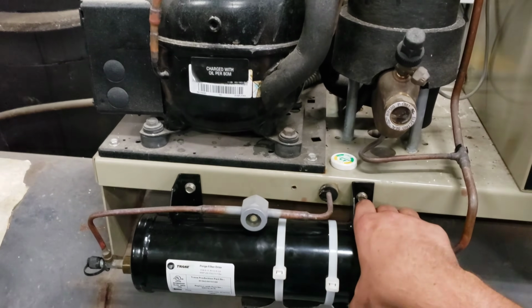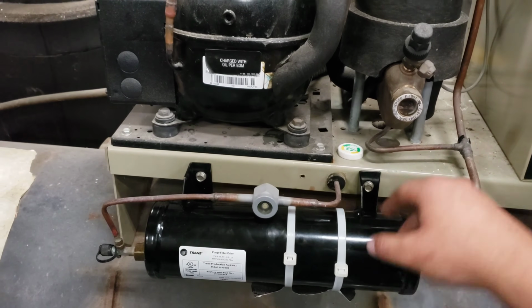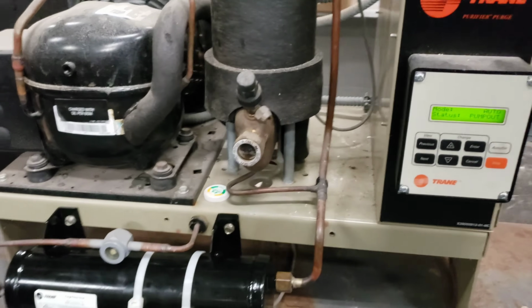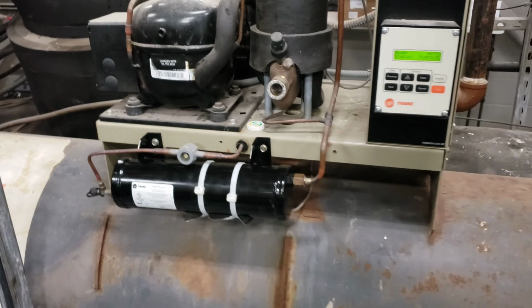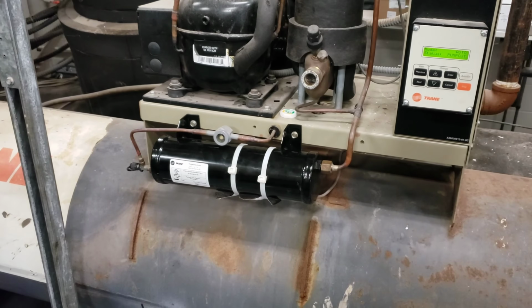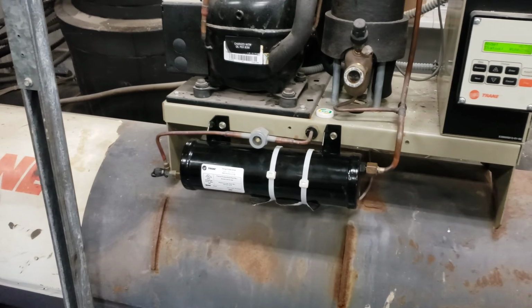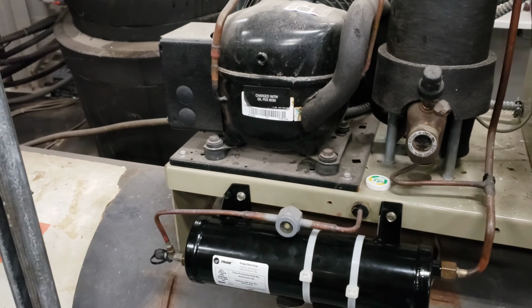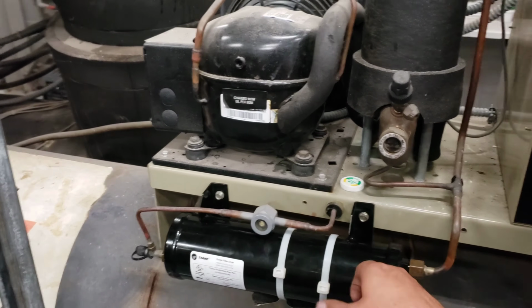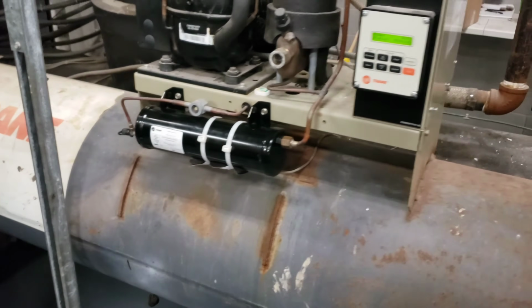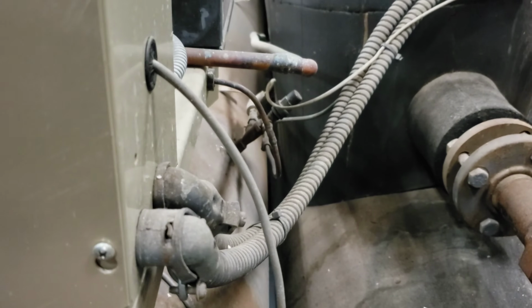So the chiller would sit there and run, never would get the purge to come on. This filter hadn't been changed in forever, and it was because the valves on it wouldn't seal off. Come to find out, after working on the valves, I finally got them to seal off enough where I could change it. But I still need to recommend replacing those service valves. You can see them back here. There's the liquid return valve, and the discharge gas valve is right back there.